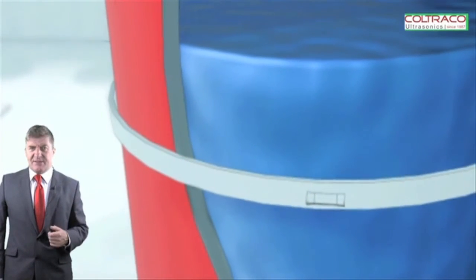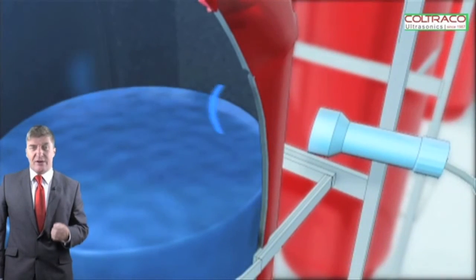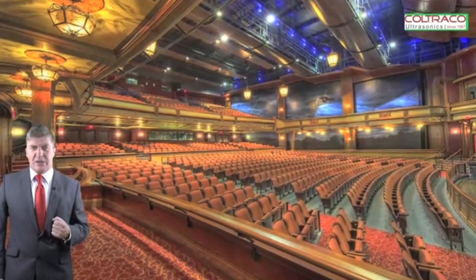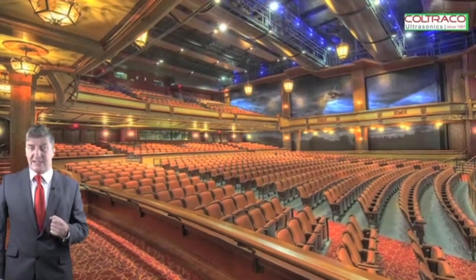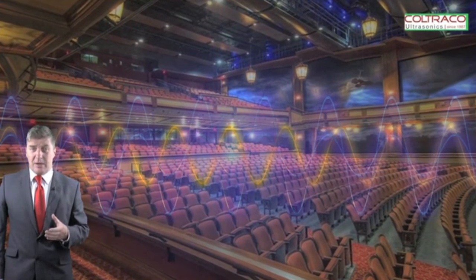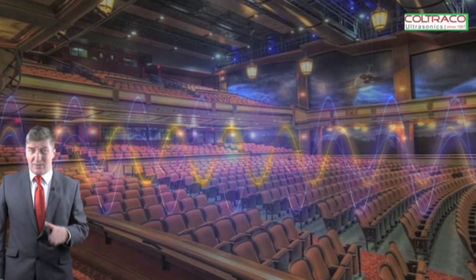There is also a facility for testing rusted or fixed cylinders — they simply increase the output signal and the sensitivity of the resulting signal. This ultrasonic sound technology can also be used to test the integrity of a room: will it hold the gaseous agent, or does it have leaks? The old way was to fill the room with smoke, which was not ideal. The modern method uses ultrasonic technology — transmitting sound in a room and placing sensors on the outside to listen for leaks, or doing it in reverse.